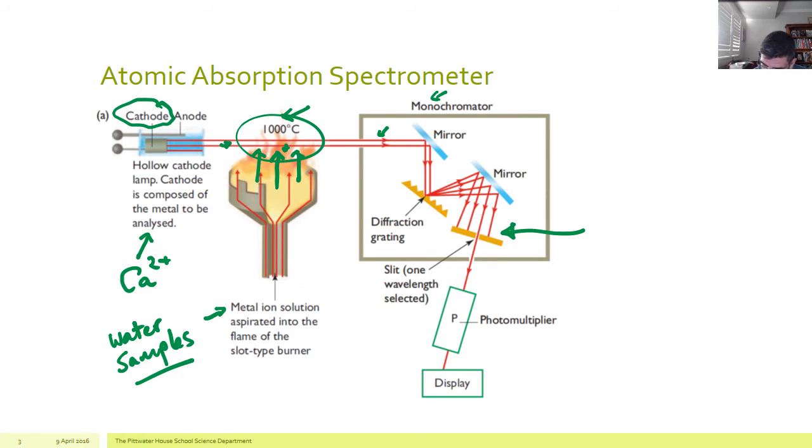For calcium, for example, this would correspond to a wavelength of about 422 nanometers. So that would be the wavelength that would come out. It would pass through a slit in the monochromator and into a photomultiplier.